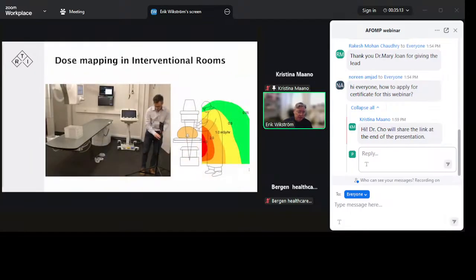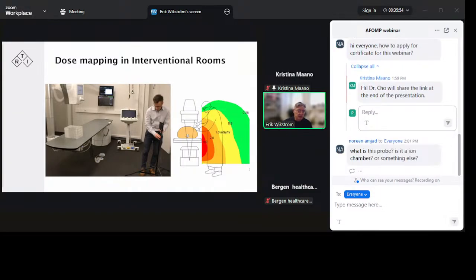And inside the room, of course, we can make a dose map, to see what it looks like. Where do we have radiation, and how is it propagated in the room? So we can make a heat map to see what it looks like in the room. Do we take the proper precautions when working with interventional systems, for instance? Then the probe needs to be inside the room, and for those occasions, it's pretty good to have the possibility of placing it on a tripod, so you don't need to stand in the room and expose yourself to radiation. So those are the basics of leakage and scatter measurements.